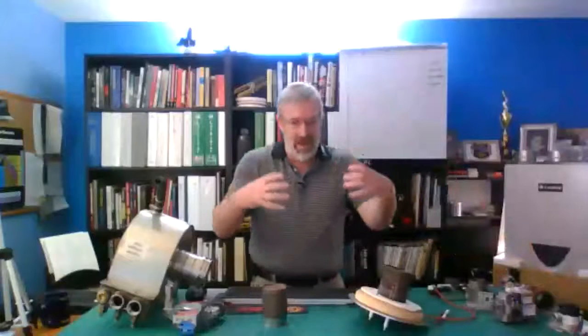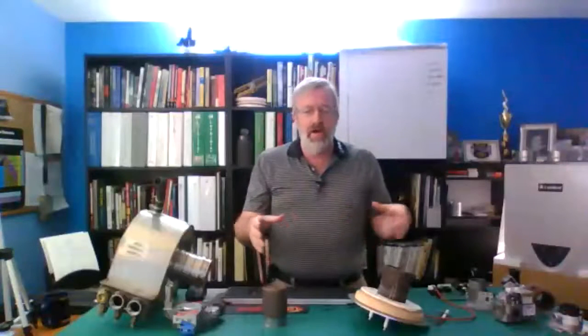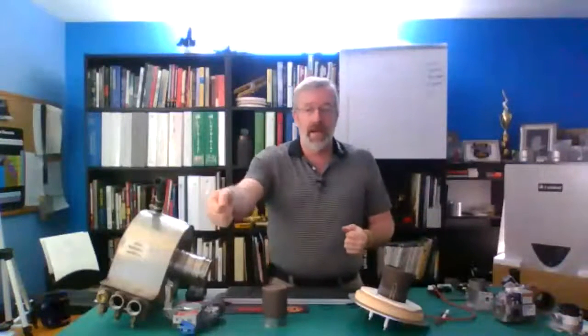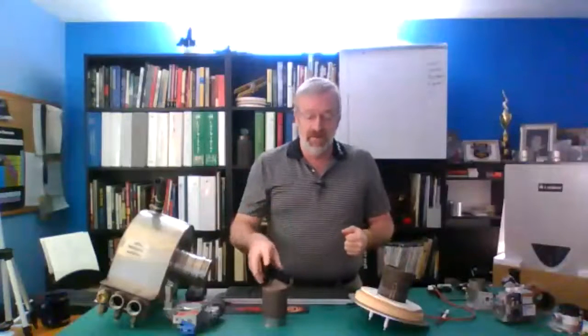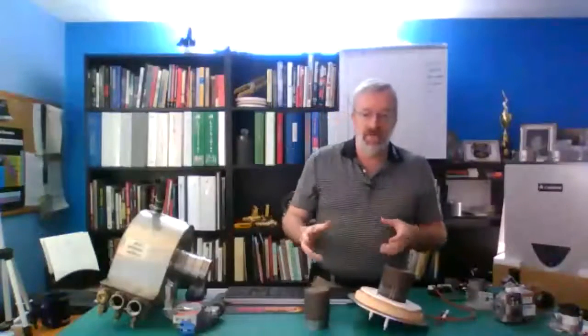Now, I want to stop like right here because it's an important part. So we got a little bit of combustion analysis downstairs, but the important thing is a lot of times people will go out, oh, my combustion's off, I'm going to put my analyzer on and I'm going to adjust my gas valve. But this is the problem. If this is dirty and you adjust your gas valve for a dirty burner, eventually when you clean the burner, your gas valve is going to be out of adjustment. So just some important things to consider there as you're working through those sort of things.